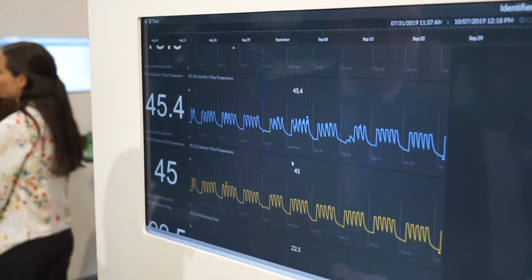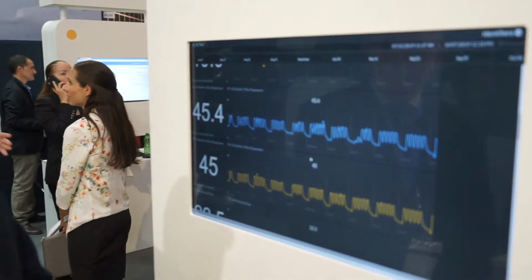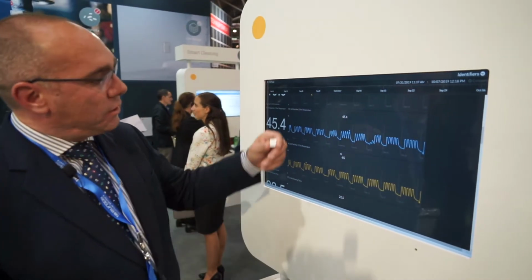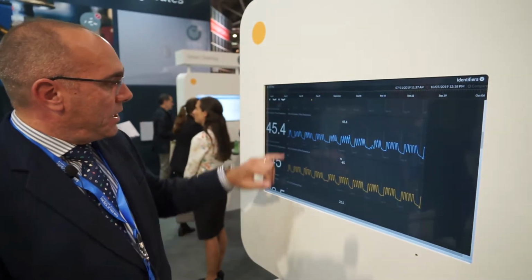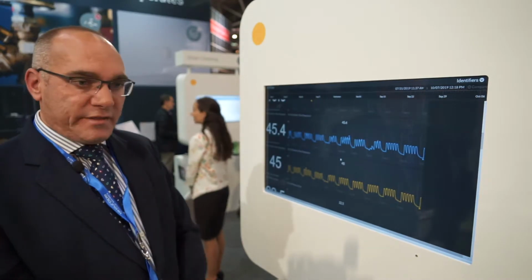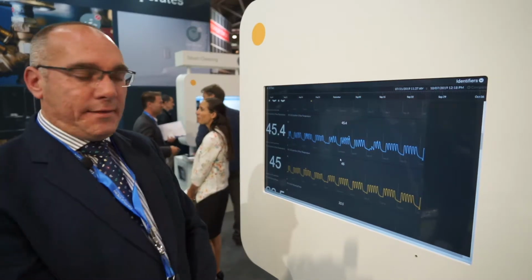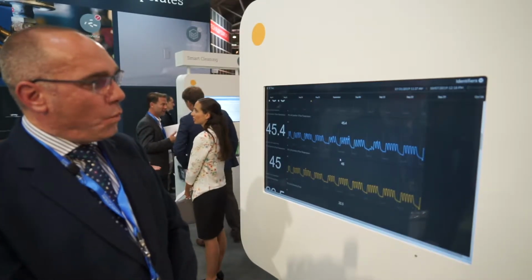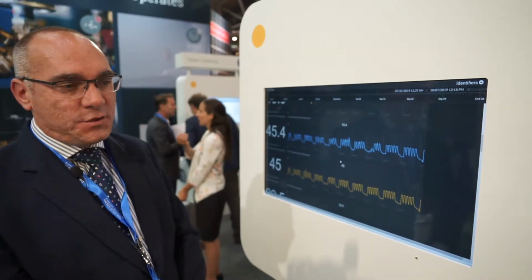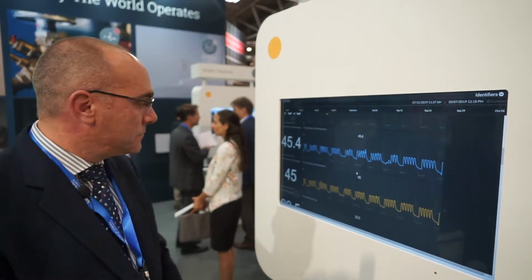We'll talk more about compliance monitoring type items where you look at calorifiers or hot water services. In this particular example, we're monitoring with the Disruptive technology temperature sensor the hot water flows of 2 calorifier units. With Legionella monitoring in particular, we can utilize that data to see if there's any drop-offs in temperature and when the systems are failing. What we do with that data is flag it to any engineering or service team to let them know that there's a problem in real time.